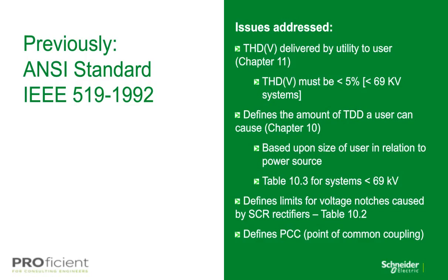And then lastly, the PCC, also known as the point of common coupling, in 1992. At that point, the definition of PCC was that the recommendation described in the document attempts to reduce the harmonic effects at any point in the entire system by establishing limits on certain harmonic indices, currents and voltages at the point of common coupling, a point of metering, or any point, as long as both the utility and the consumer can either access the point for direct measurement of harmonic indices meaningful to both, or can estimate the harmonic indices at a point of interference, POI, through mutually agreeable methods. With an industrial plant, the PCC is the point between the nonlinear load and other loads.